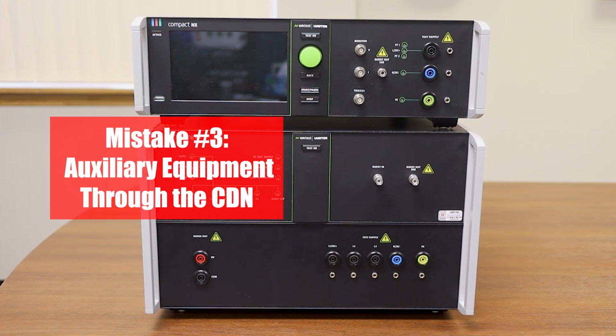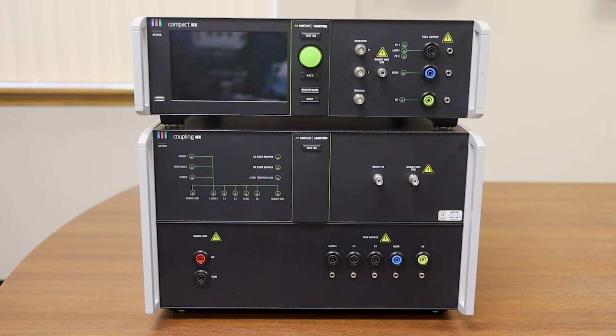Depending on the needs of the equipment under test, it can require multiple power or data connections for normal operation, which is typically how testing is conducted. This can lead to a situation where multiple connections will need to be run through the coupling-decoupling network. If they're not, surges can be transmitted from the equipment under test to the auxiliary equipment, then to our mains power.